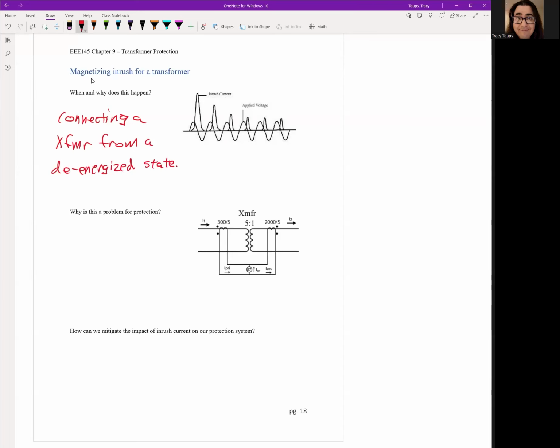Now, this is important because if you take a transformer and you turn it off and turn it back on really quick, it hasn't had enough time to lose its magnetic field, so you won't have this issue. But if you turn off the transformer and wait a couple of hours or 24 hours, then it'll lose its magnetic fields, it'll lose its stored energy, and then you're going to have to do this whole inrush issue when you re-energize the next day. So connecting a transformer from a de-energized state means we need to energize the coils in the transformer, right? Again, we can't get away from this. We have to do it.